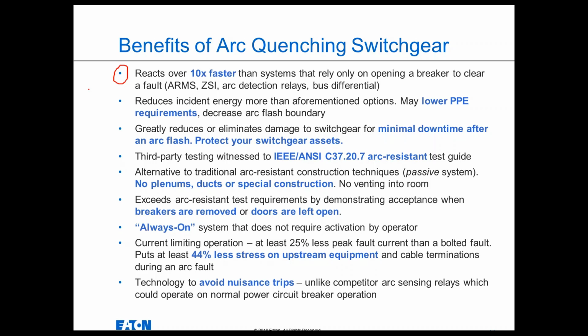As Chris explained, when a feeder breaker clears a downstream fault, a bunch of arc light will come out of the back of that circuit breaker. And that'll cause most arc detection systems to nuisance operate, because traditionally arc detection systems look for light and current. So when there's a downstream fault, there's high current, so the arc detection relay sort of checks that box, says, yep, I've got high current. Then the main contacts in the breaker part. A bunch of light comes out of the back of the circuit breaker. The relay says, oh, I also have light. I've got light and current. It must be an arc flash. And then it sends a trip signal to the upstream breaker, that main breaker, and takes the whole board offline. When really, you just wanted that feeder breaker to clear the downstream fault, maybe something going on in the MCC. So that's how a typical arc detection system would react.